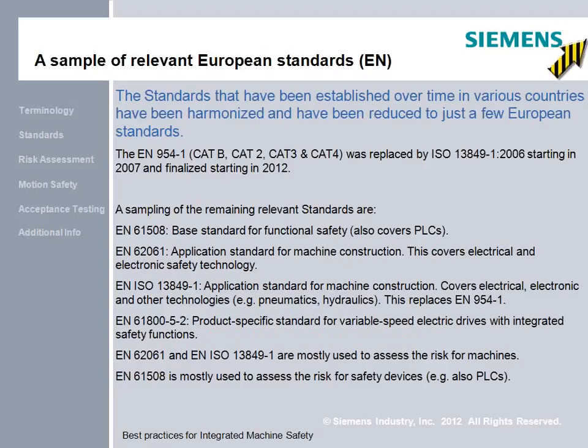A brief look at the European standards. You must note that EN 954-1 has been removed. Starting several years ago, ISO 13849-1 2006 was implemented with the goal of replacing EN 954-1. That process started in 2007. That process of replacing EN 954-1 completed at the end of 2011.